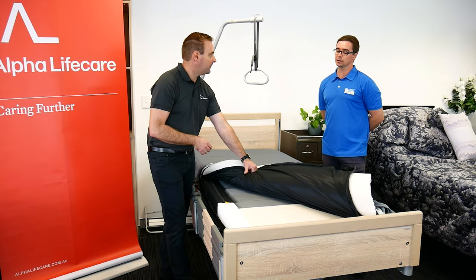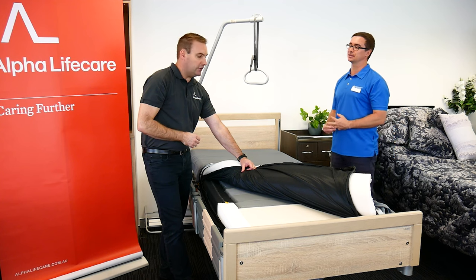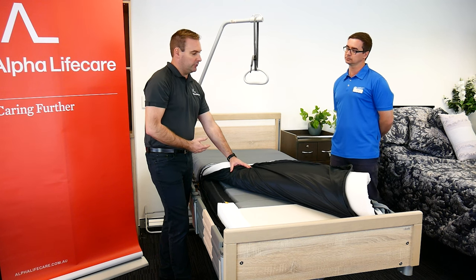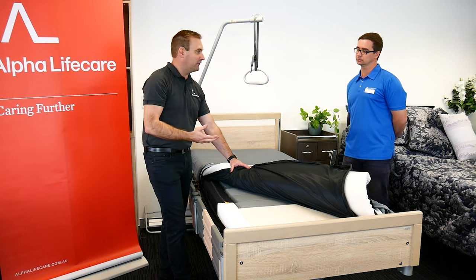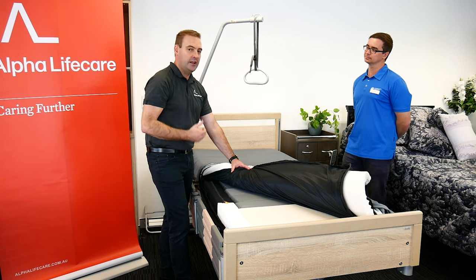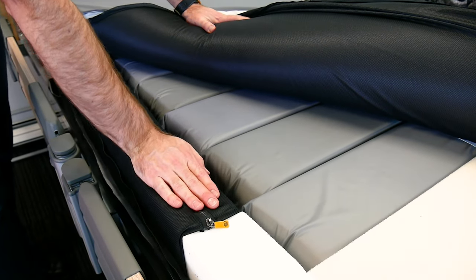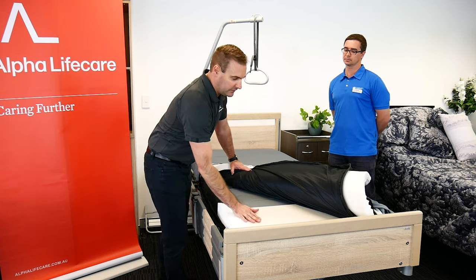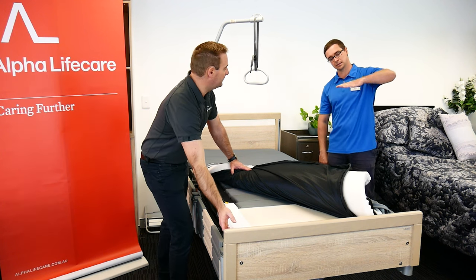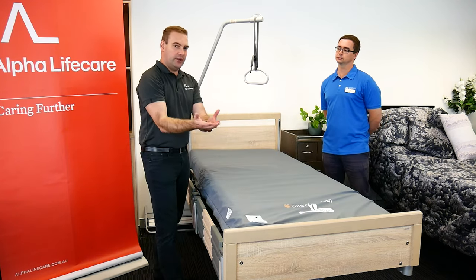It's a great weight range. How does an occupational therapist usually trial this product? It is available for a trial period — typically one week. Getting a new mattress you often don't sleep well the first night, so it's a good way to trial it for a few nights, find out if it's helping your pressure care and your sleeping. It's got a solid core perimeter so it's great to test transfers. It also has a feature called the heel slope — the mattress actually tapers off at a slight slope and gets thinner, moving the weight of the heel back up onto the calf.